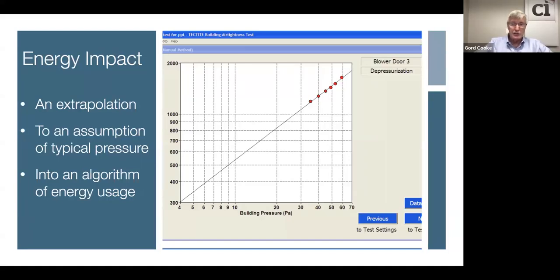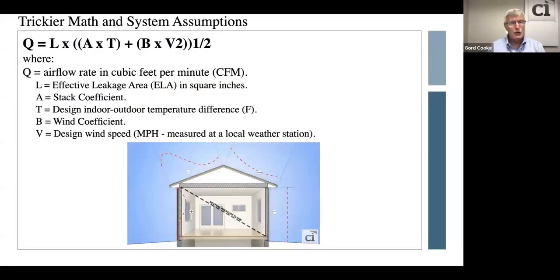And then you would use a series of algorithms to turn that into energy use. And I'll show you some of the math. It is fairly tricky math. It's what's called the effective leakage area at 5 pascals of pressure.